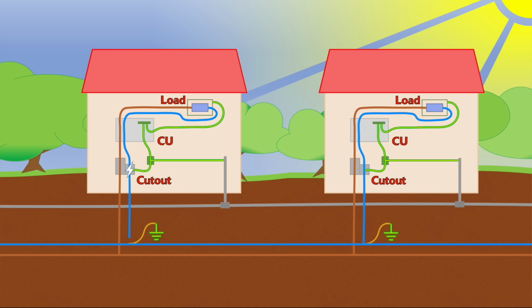Now, this is the point where the neutral and earth conductors are combined. They literally join together and become the same conductor. Now, however, the current can't carry on down the supply cable because it's got nowhere to go. However, it does have this handy earthing conductor to travel along. Then it finds it can flow along this bonding conductor to this metallic water pipe. It can now leave the property and travel along the pipe.